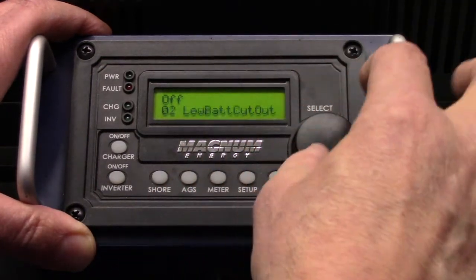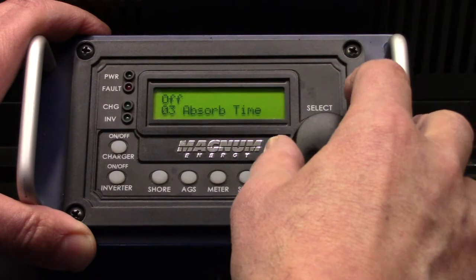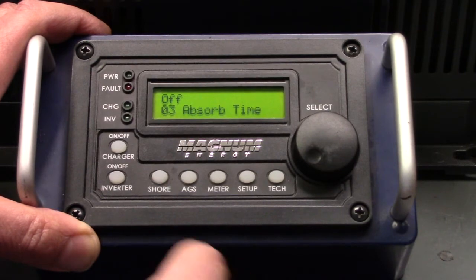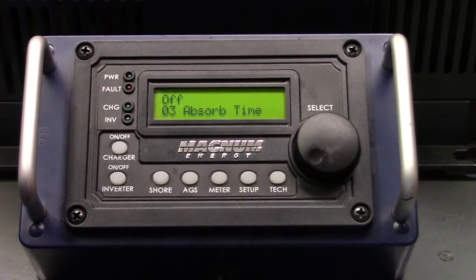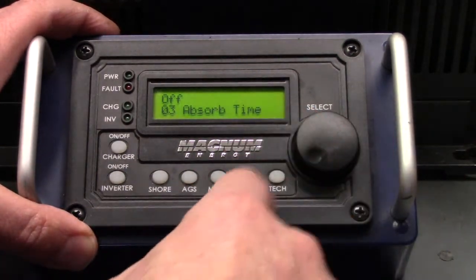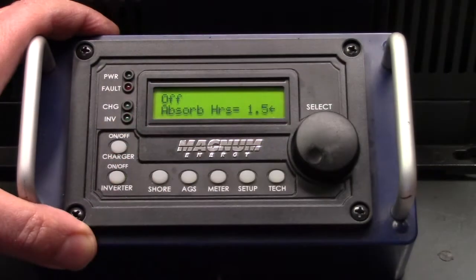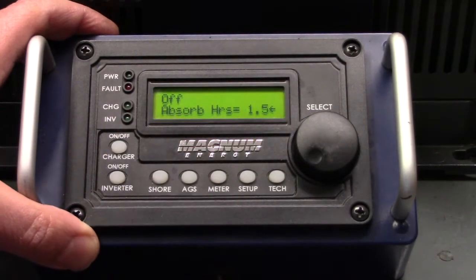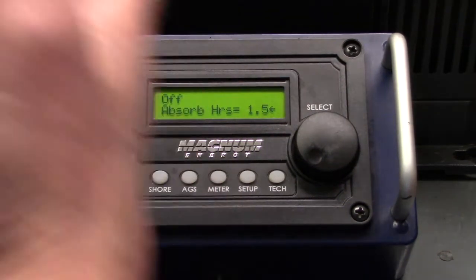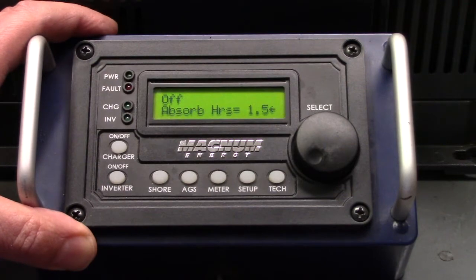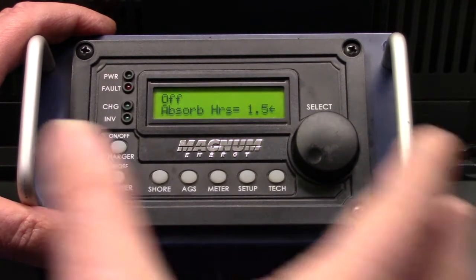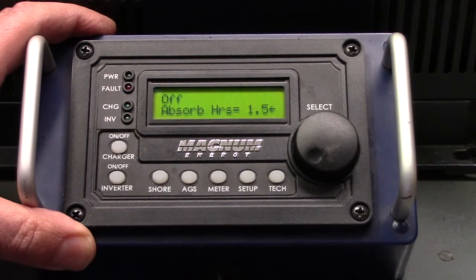Let's go back in the setup—search watts, low battery cutout, absorb time. You do want to check this one based on the size of your battery pack. If you have the typical 4 battery pack, 4 six-volt batteries, then the factory default of 1.5 hours is fine. This is the amount of time you want the batteries to be in what they call absorb during the charge cycle, where it simply holds a voltage for a certain amount of time to make sure the entire battery pack gets charged, and then the charger shuts down.